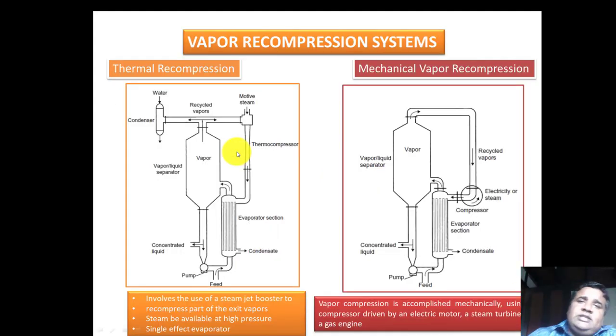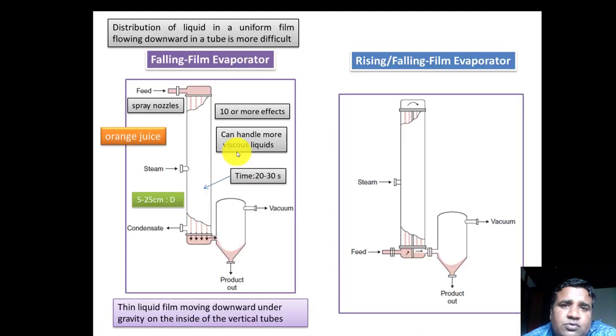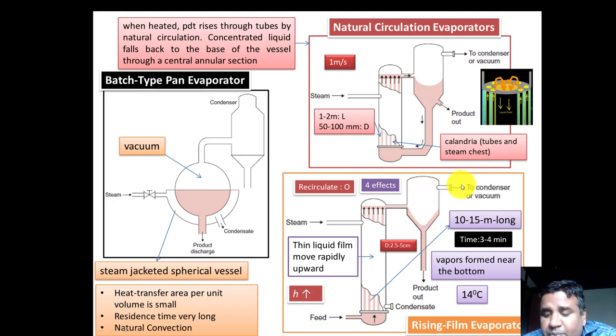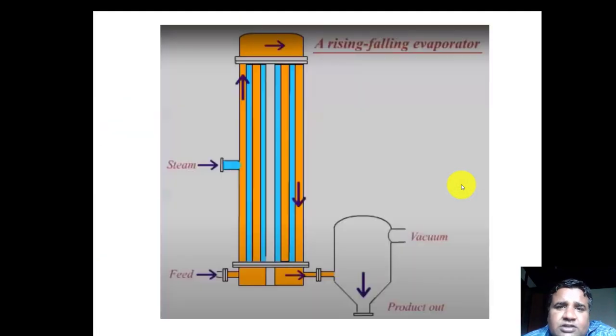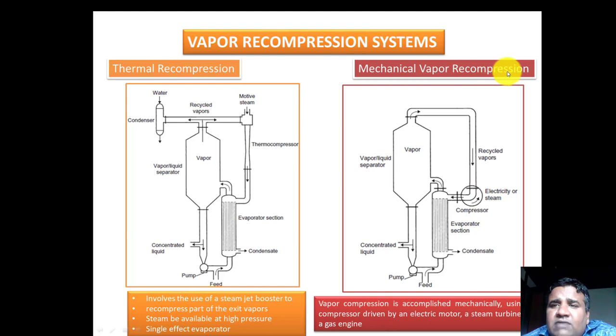Now I am coming to vapor recompression systems. Why is vapor recompression required? We studied multiple effect evaporators. The vapor collected from the separator is not at a high temperature. To increase the temperature of this vapor coming out, we have two provisions: either thermal recompression or mechanical vapor recompression. The vapor generated from the first effect is collected — it is not at high temperature — so we need to recompress it.